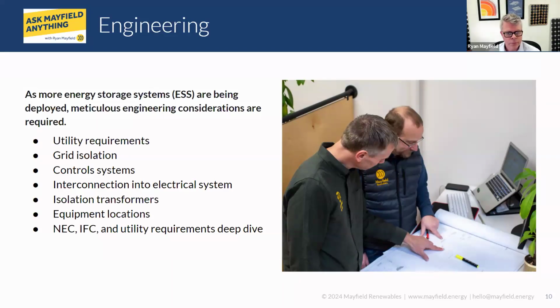Yeah, and I guess just to kind of finish going down the list - equipment locations, which can be dictated by code, maybe the NEC requirements or utility requirements for disconnects, where the batteries can be based on the fire code, the IFC. So there's a lot to think about there, where everything's going to go, where you're going to put these different pieces of equipment. Then you go through all the different iterations and codes, making sure you're satisfying the requirements of the NEC, the fire code, and the utility requirements as you move through the design process.